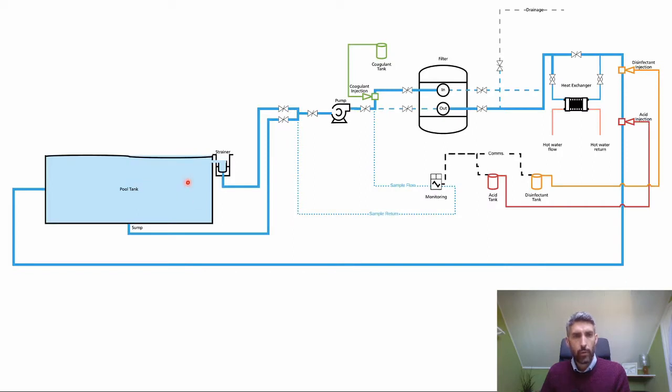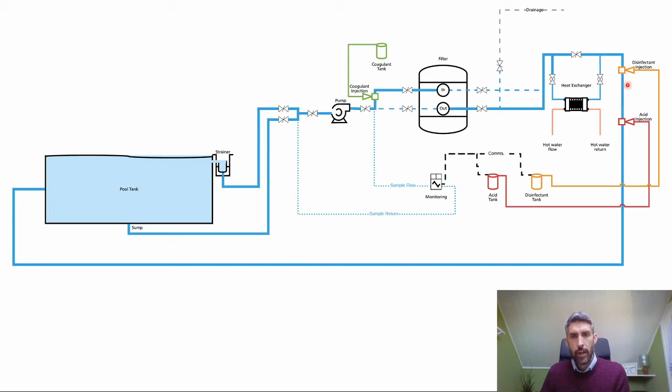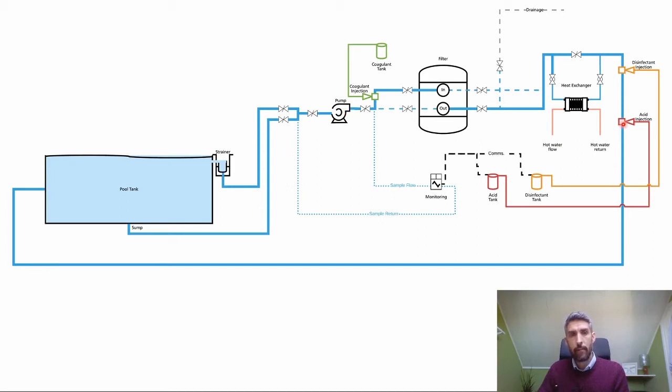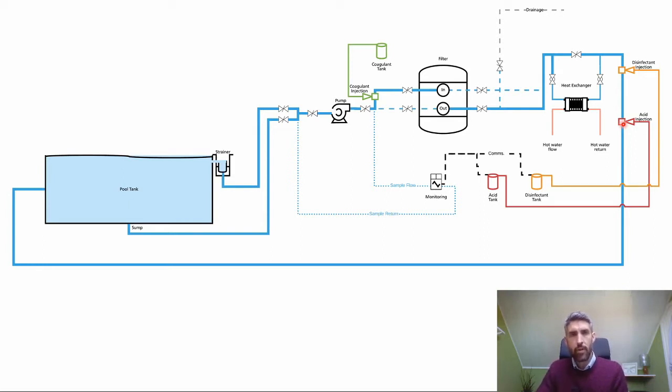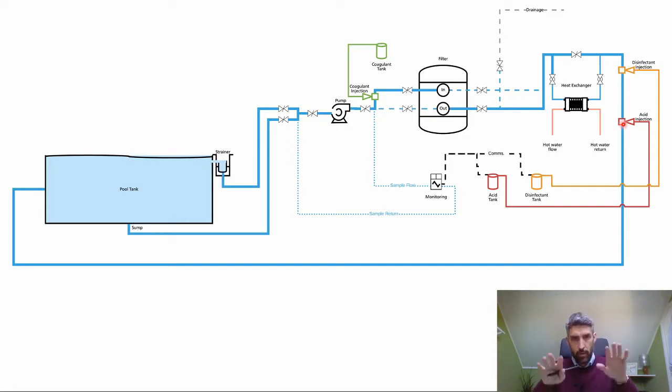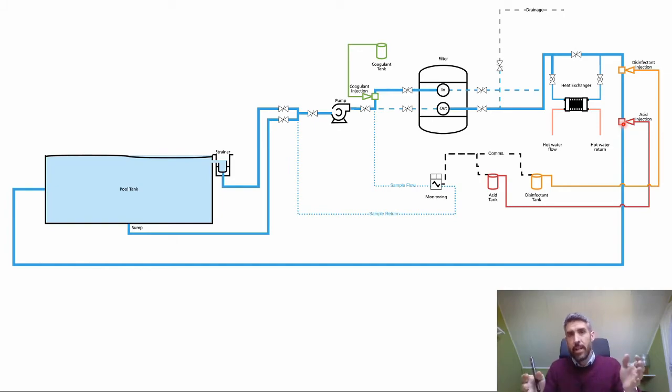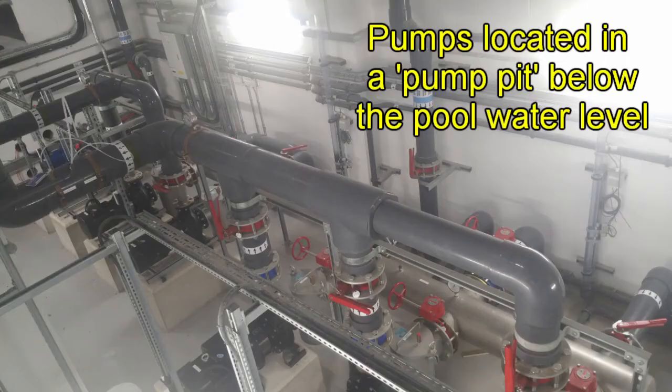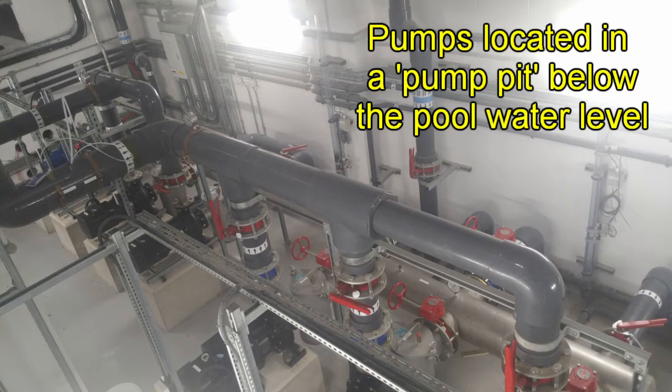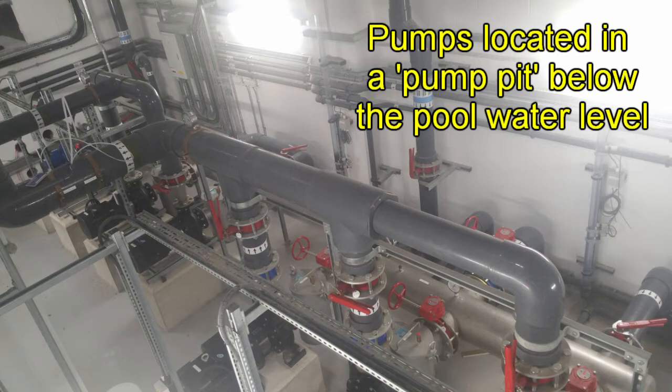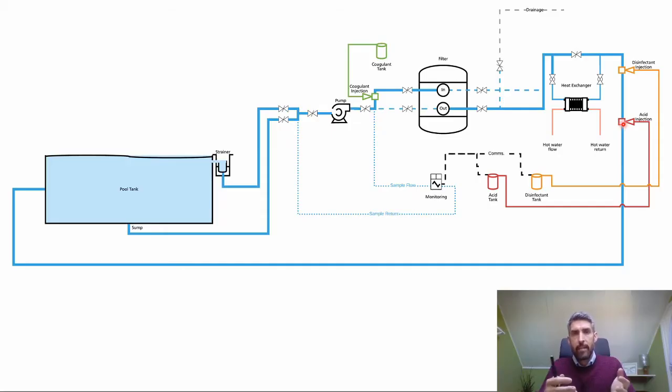For example, you've got your pool tank and the water level comes to this level here. You can see above the water level you've got your pumps, filters, and injection points as well. In most plant rooms the equipment is below the level of the swimming pool. What that does is creates a head of pressure because of gravity, so that if the circulation was to stop you wouldn't lose prime because all of that pipework would remain flooded.